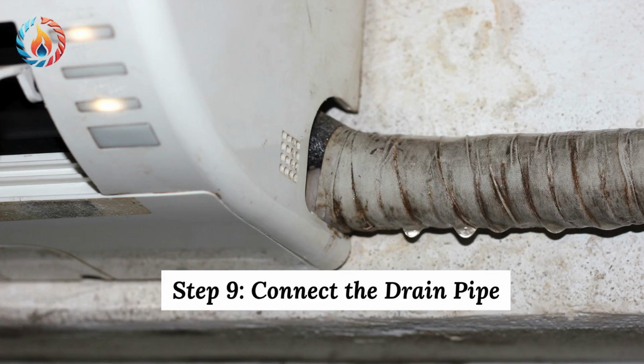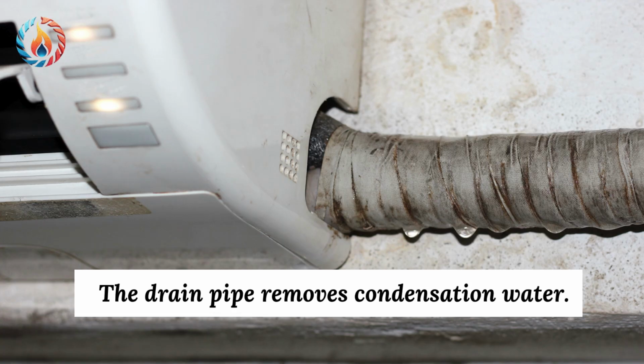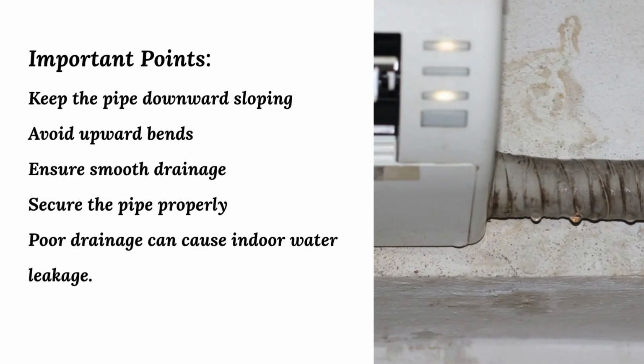Step 9. Connect the drain pipe. The drain pipe removes condensation water. Important points. Keep the pipe downward sloping. Avoid upward bends. Ensure smooth drainage. Secure the pipe properly. Poor drainage can cause indoor water leakage.